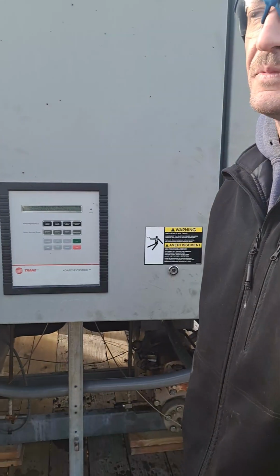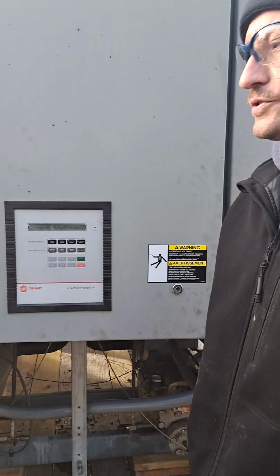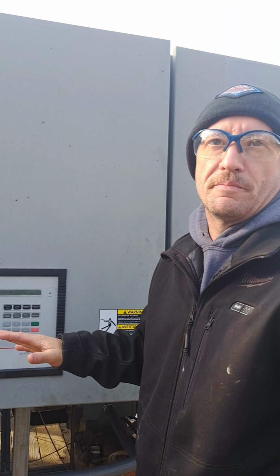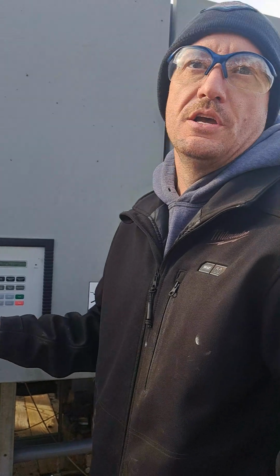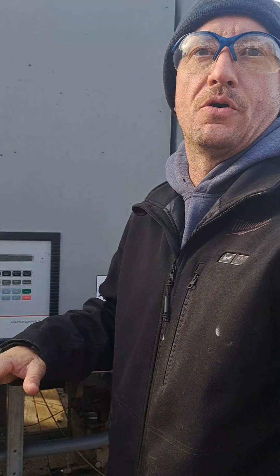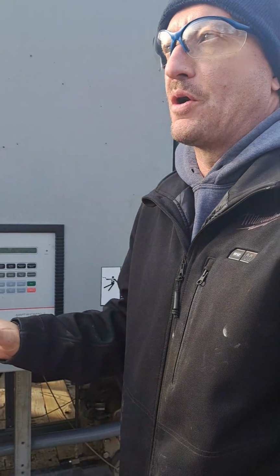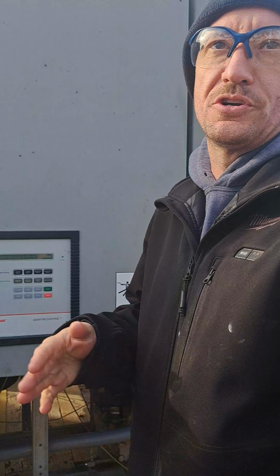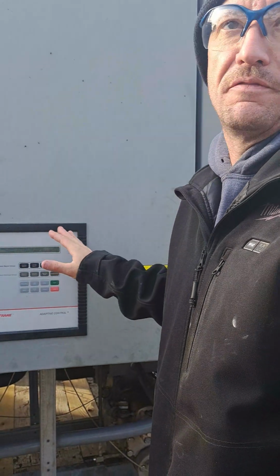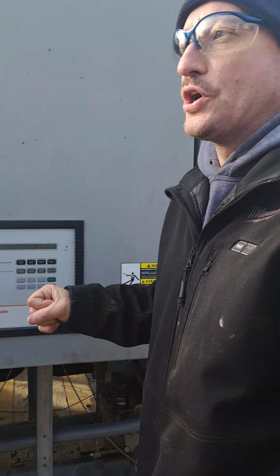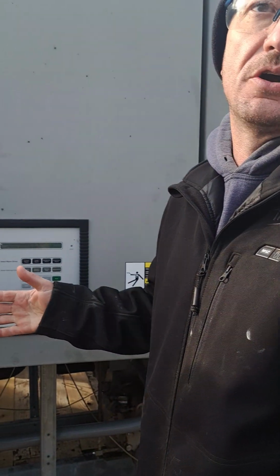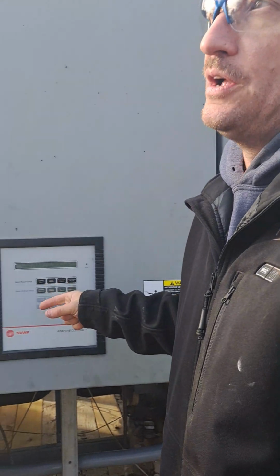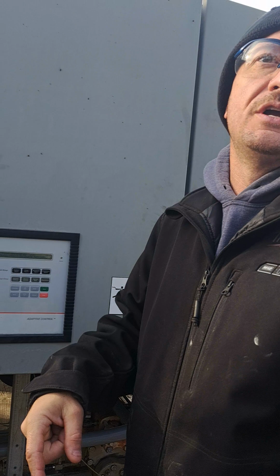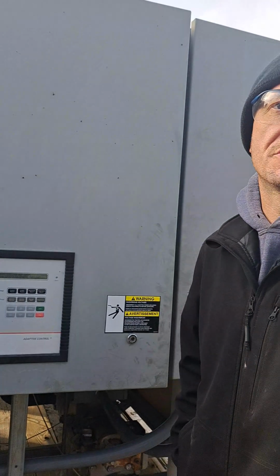Why would we need to, or is that something? Probably not. Yeah, tell us what you told us yesterday about the set points. So these things, they're only designed for a certain amount of tonnage. So turning your glycol temperature down to 0 degrees does not get you any more refrigeration. So don't let people come over here and say, we got water on the ice, turn it down, it'll freeze. That's not the way it works. So you're dependent on outdoor temperature, sun loading, and just the capacity of this chiller, whatever that is. So turning down to 0 is not going to get you anything better. In fact, it'll actually cause this machine to lock out because your refrigerant pressures are going to run lower, and then it's going to start locking out on safeties. Okay. So it's going to try to protect itself.